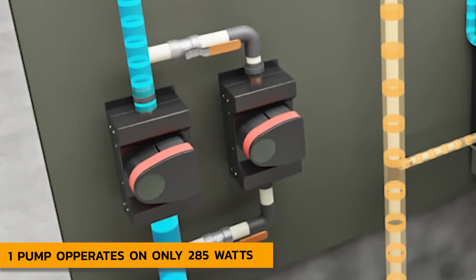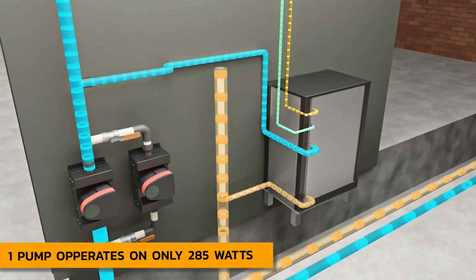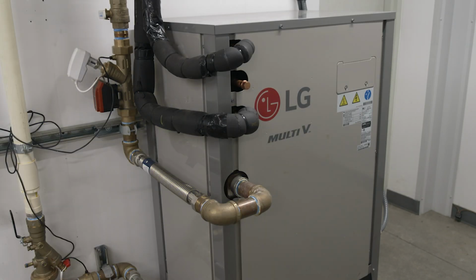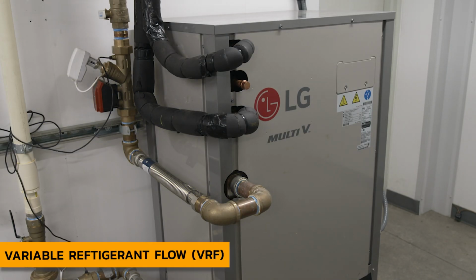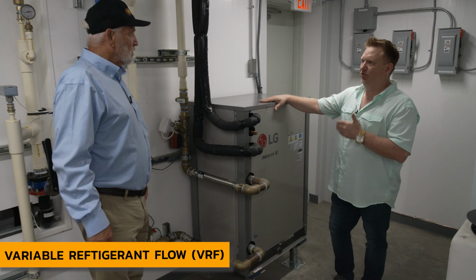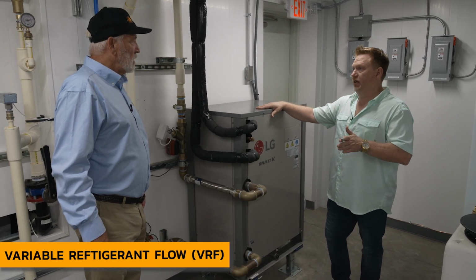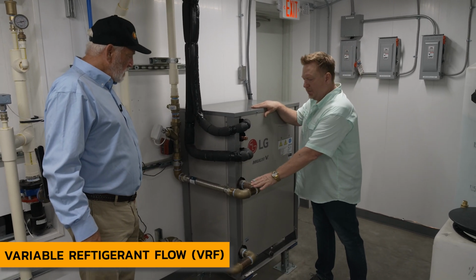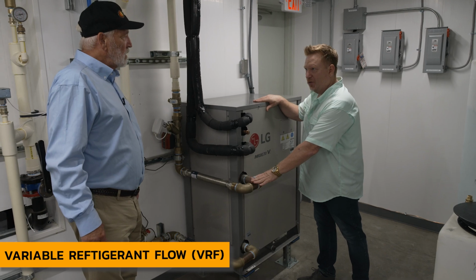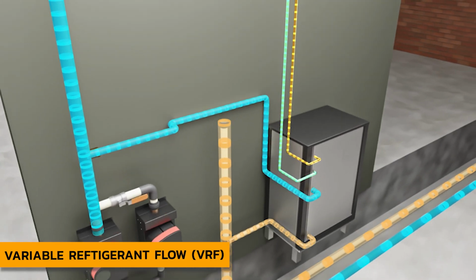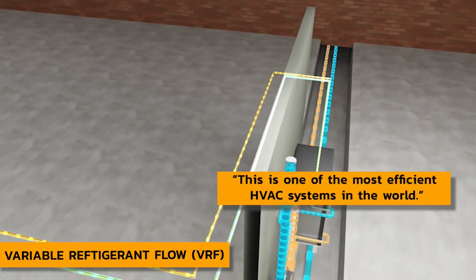This whole system is being powered by 285 watts. That's 3 light bulbs. We can do the entire cooling with this single water-cooled unit. It's called a VRF unit, variable refrigerant flow. Variable refrigerant flow units are highly efficient anyway, and when you combine that with geothermal cooling, this is one of the most efficient HVAC systems in the world.